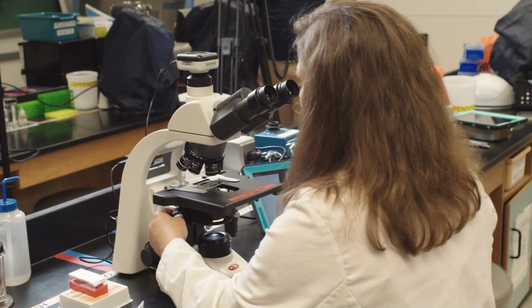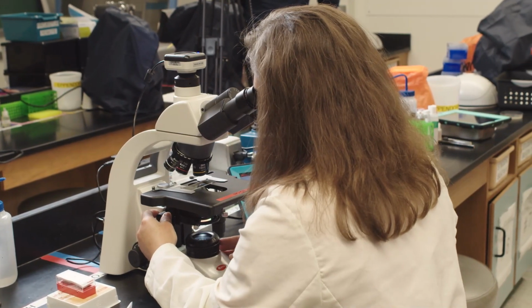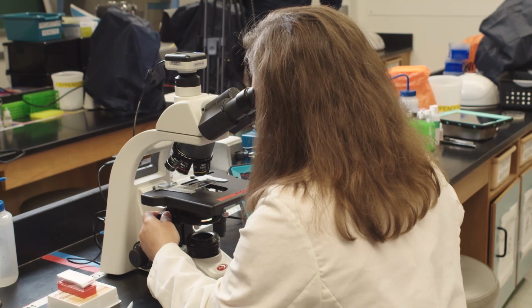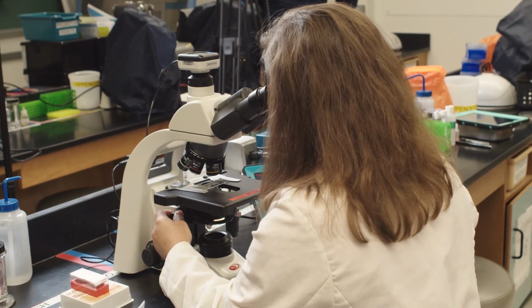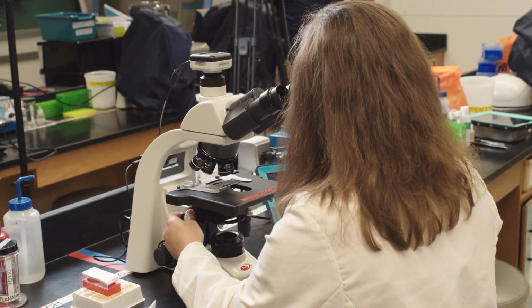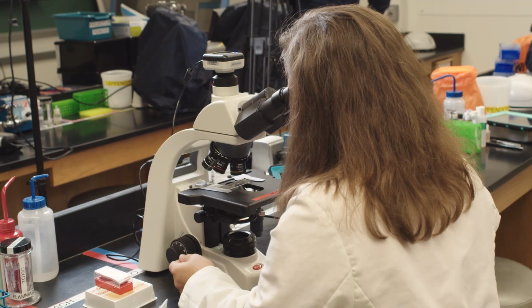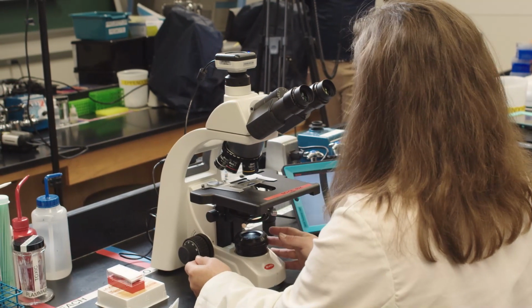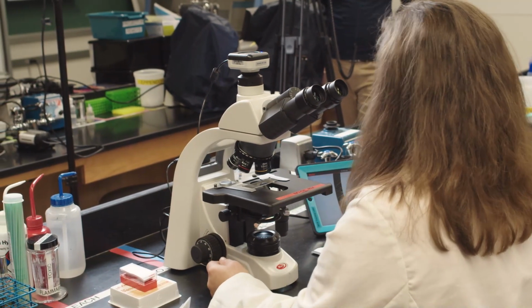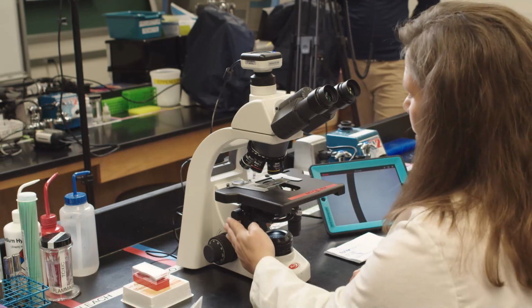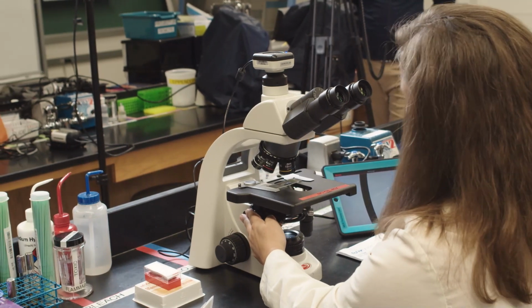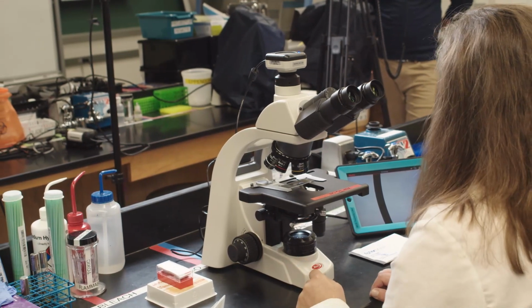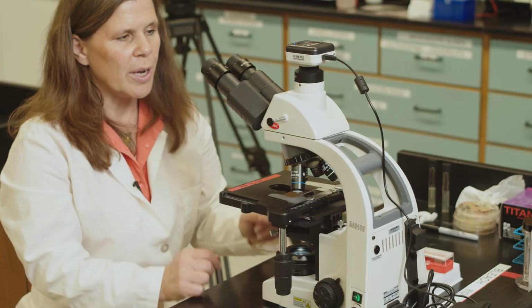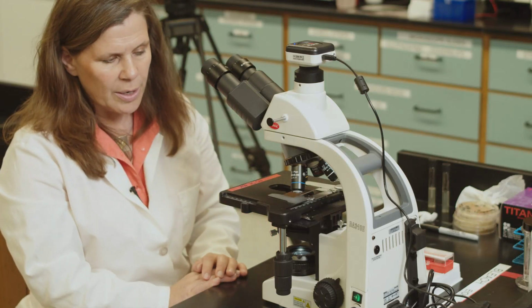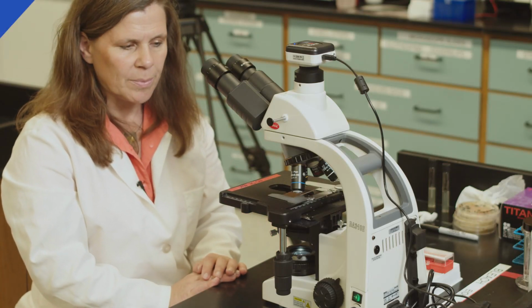You adjust the condenser height. You close your field diaphragm and adjust the condenser. You see a clear polygon in the middle. Then you open your field diaphragm and you're ready to do microscopy. Once you have the condenser set, you don't touch that anymore. It stays. But make sure you have a clear view and you keep the microscope clean.